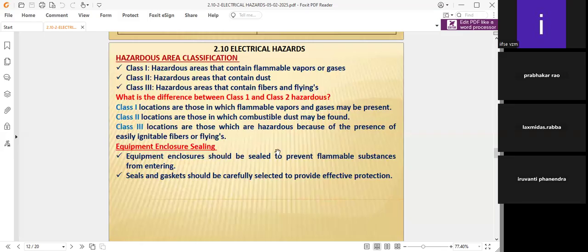Dust is not supposed to accumulate on the circuits inside the panel board either. We have to close the doors perfectly, and there should not be any dust accumulated on the circuits. What you said is that it is also flammable during ignition. Okay, sir. Coming to this, the hazardous area containing fibers and flyings is where cotton industries and textile industries have fine particles flying in the atmosphere, which are also combustible and flammable. Thereby, near the electrical panels, it will definitely catch fire.